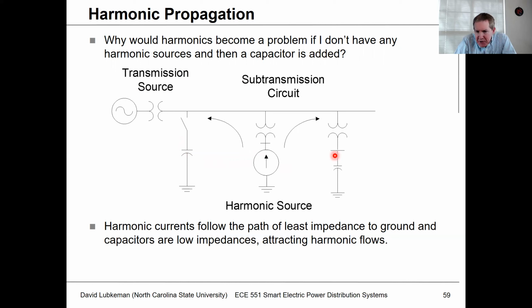So normally what happens if I have power factor correction capacitors in a circuit, or power factor correction capacitors on the customer side of transformers, that if I had a harmonic producing source, a lot of times these currents are going to tend to want to sink where we have capacitors in the circuit. If I don't have the capacitors, that's going to sink toward the source. But if I have capacitors in there, those capacitors are going to be subject to harmonic issues. And so capacitances and harmonic sources don't really mix too well. This is where you have to kind of start being careful.